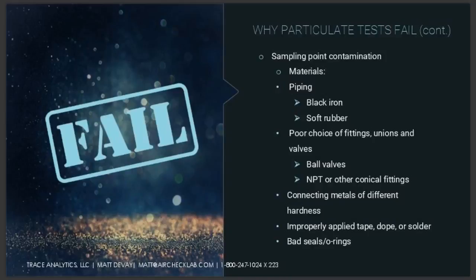Conical fittings also kind of have some problems associated with them in that they're friction-based fittings, and they have a lot of surface area to hold contamination. Avoid metals of different hardness. This is a pretty common one. You see people with aluminum systems and they're using a steel sampling point. You'll see people using copper piping, which is not necessarily a bad material to choose. But then if you're going to hook up a 1/4 inch NPT test kit, you've got to make the transition between copper and steel. So anytime that you have metals of differing hardness, the softer metal will generate particles through vibration and friction against the harder metal.